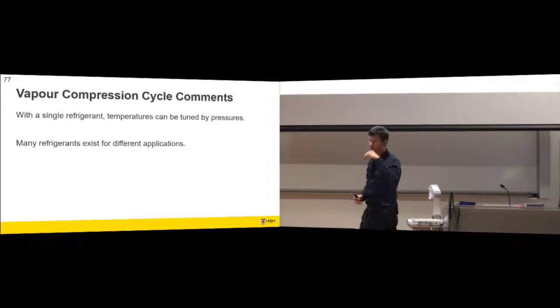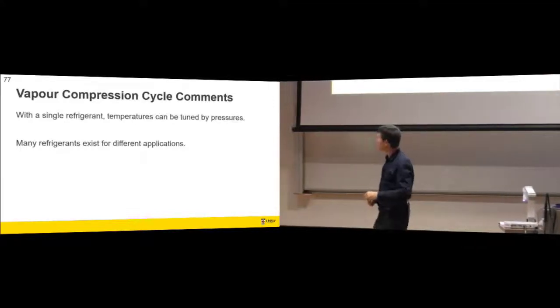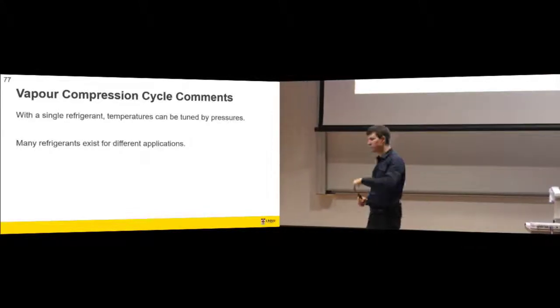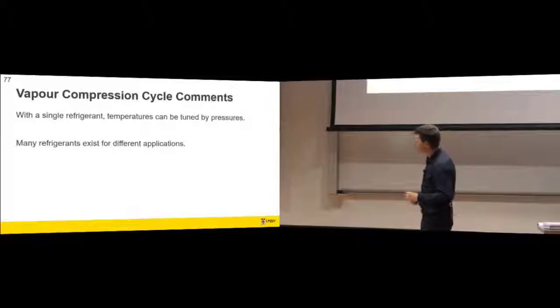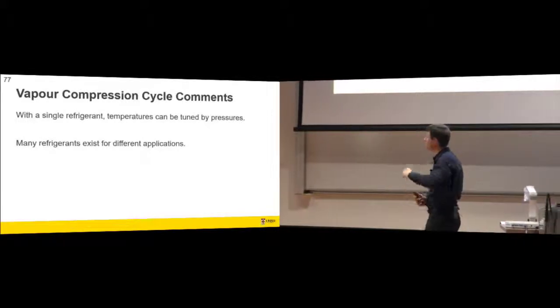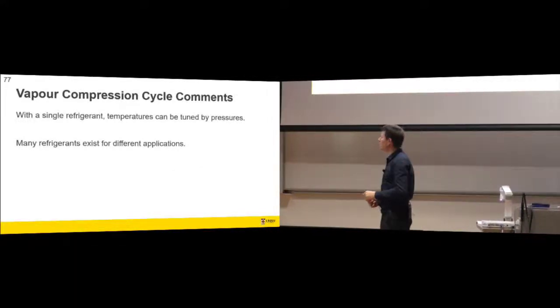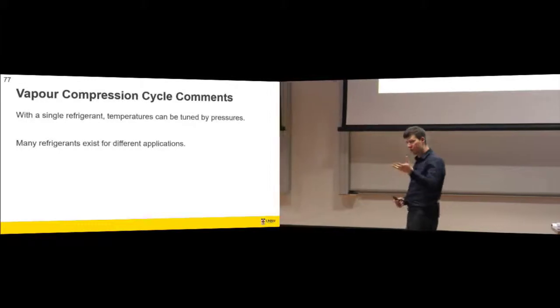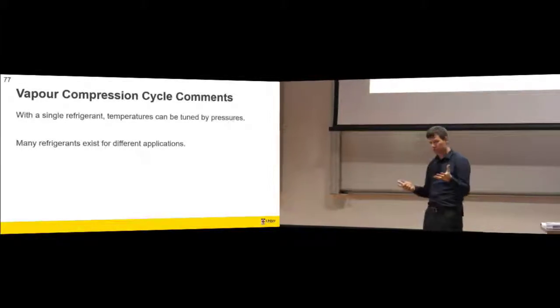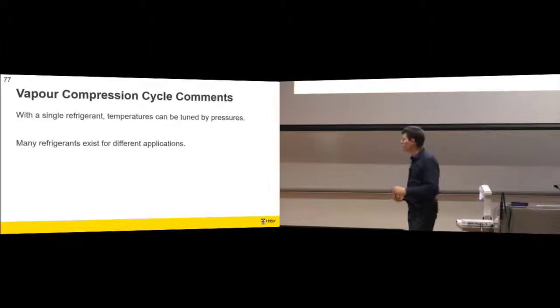For R134a, if we choose a pressure of 2.9 bar we get about zero degrees C. If we choose a pressure lower than that we'll get a lower temperature. And if you want to go lower than R134a can do, you choose a different refrigerant.